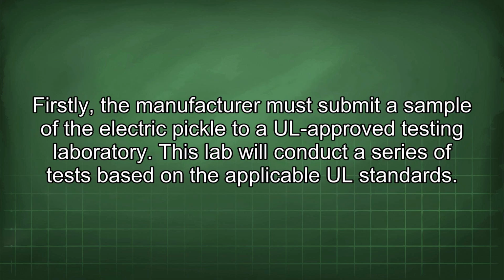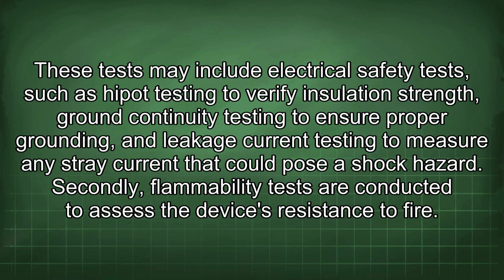Firstly, the manufacturer must submit a sample of the electric pickle to a UL-approved testing laboratory. This lab will conduct a series of tests based on the applicable UL standards. These tests may include electrical safety tests such as hipot testing to verify insulation strength, ground continuity testing to ensure proper grounding, and leakage current testing to measure any stray current that could pose a shock hazard.